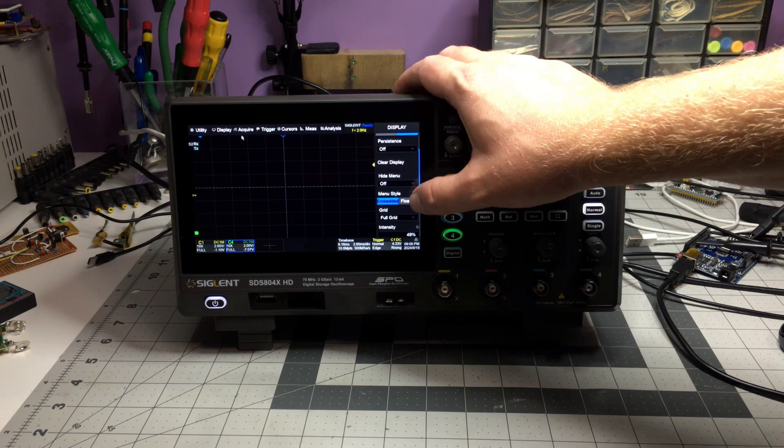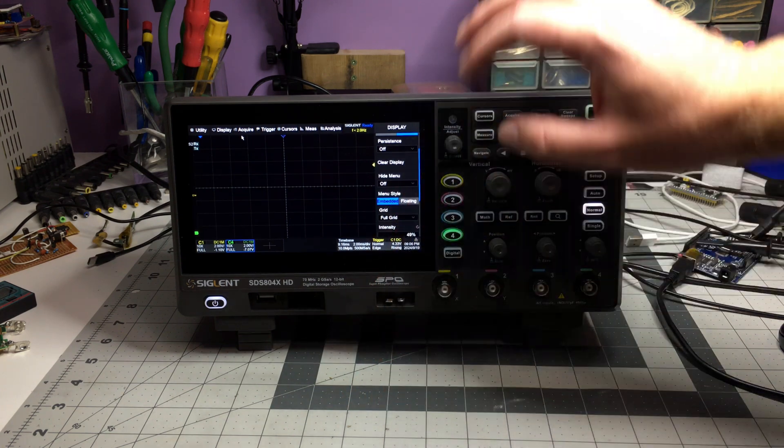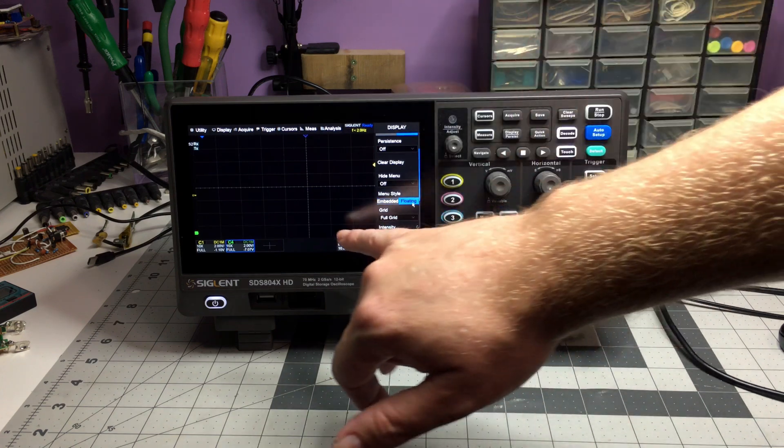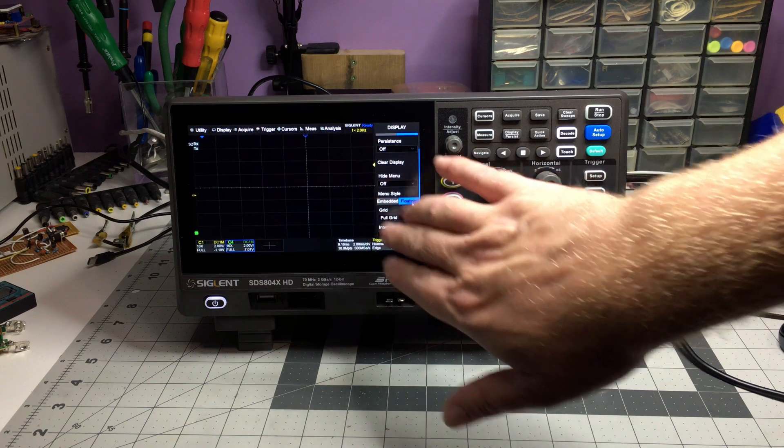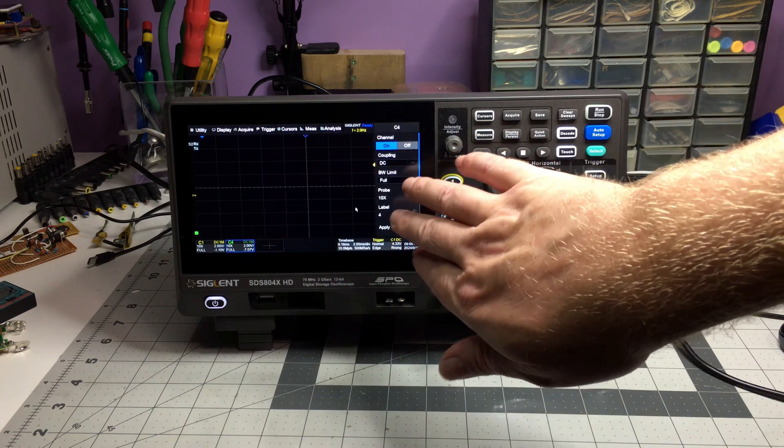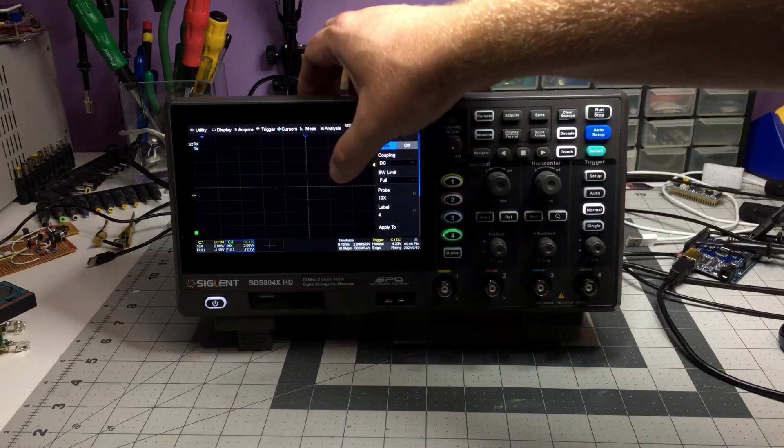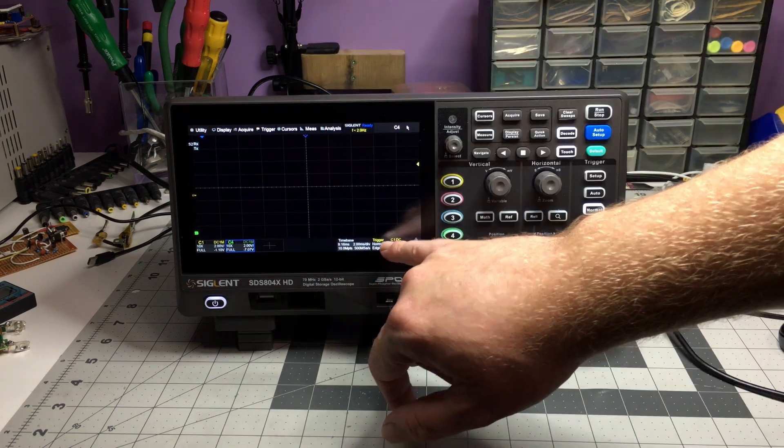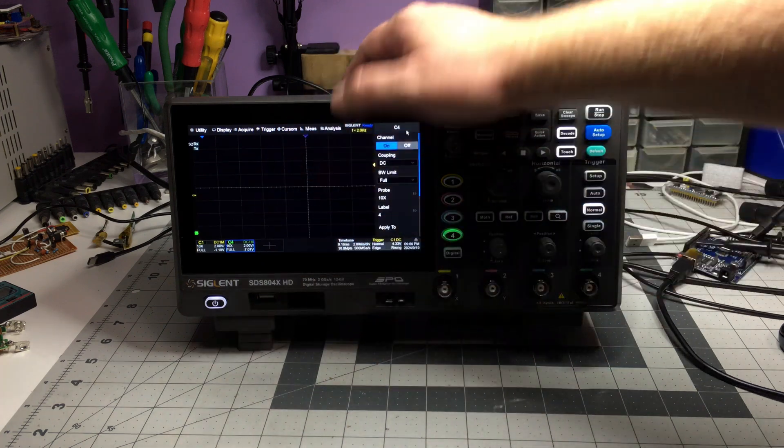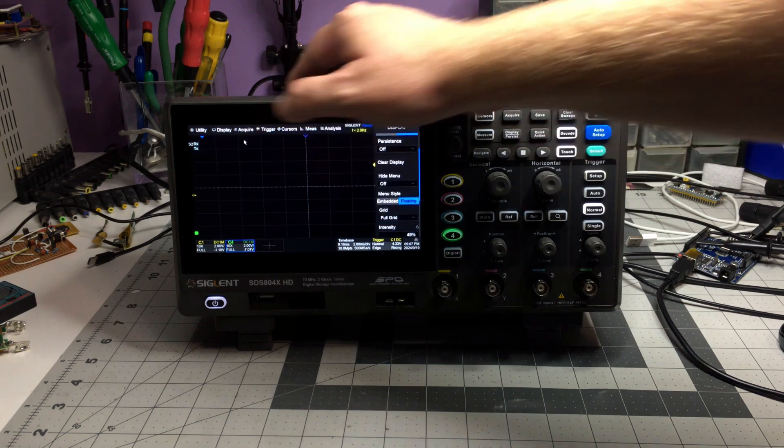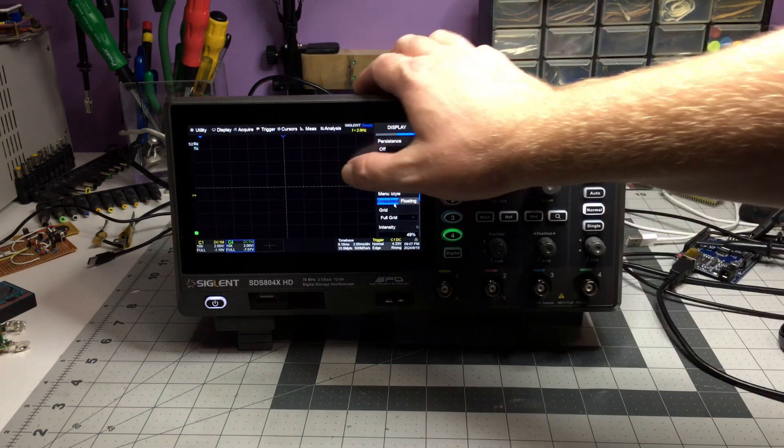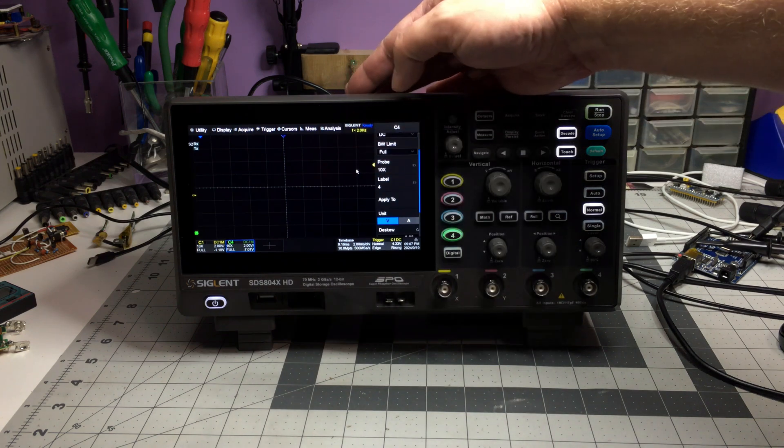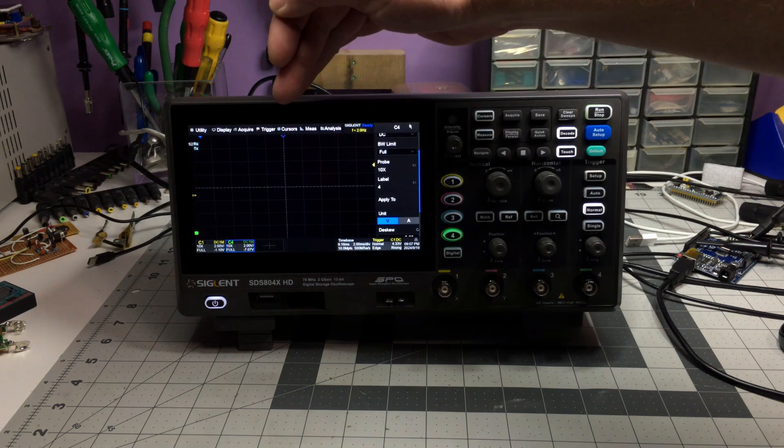The other thing is, there's two options here. One's embedded and one is floating. If you have it set to floating, then it will hide the graticules behind the menu. So you might have some information off screen that's hidden away by the menu and you won't be able to see until the menu disappears. You can see these two graticules will be hidden behind the menu. They don't shift. Then if you change that back to embedded, they do shift over and it resizes depending on whether there's a menu here or not. You can see that shifting over and making the graticules narrower.